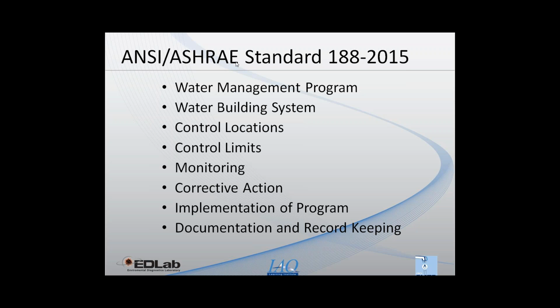Then we have to also be aware of the control location, determining the location in the system where control measures are required in case of a Legionella outbreak, and then the control limit, where for each control measure at each control location you establish a point that the physical parameter must be monitored and maintained in order to reduce the hazardous condition. So these are some good points in this standard.